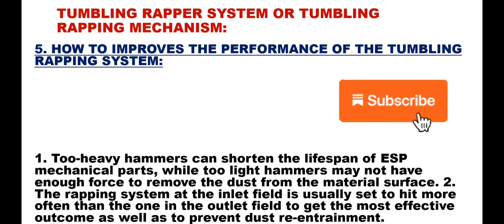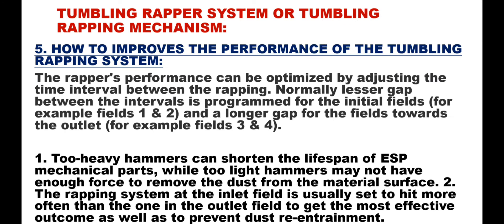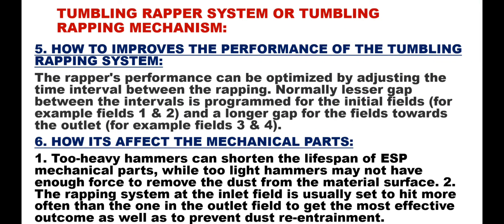Point 5 – How to improve the performance of the tumbling rapping system: The rapper's performance can be optimized by adjusting the time interval between the rappings. Normally, a lesser gap between the intervals is programmed for the initial fields — for example, fields 1 and 2 — and a longer gap for the fields towards the outlet — for example, fields 3 and 4.